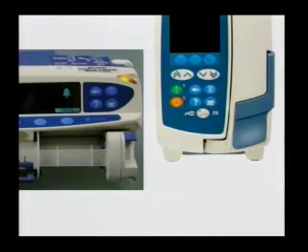Okay, so let me ask you, what do you think they do on this pump? That one. So on the syringe pump, which is the one that's got the syringe in it, they purge, they tell you the pressure, and they give you options. The same buttons are on the other pump, and the manual says they do the same things. Any suggestions? I mean, obviously, this is a setup. They don't do the same things, but what do they do? And you can imagine from the sort of intensive care picture I showed you, both of these gadgets could be plumbed into the same patient.